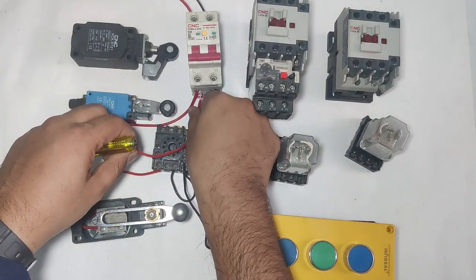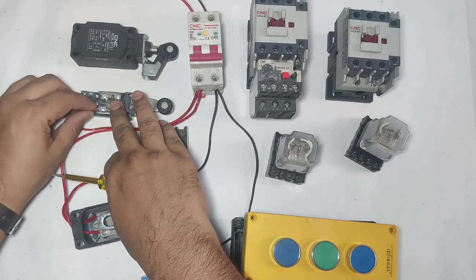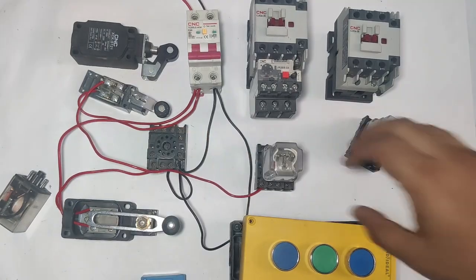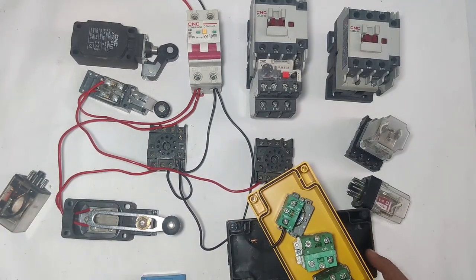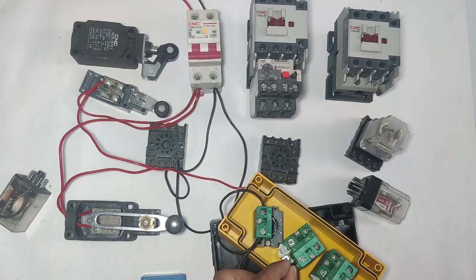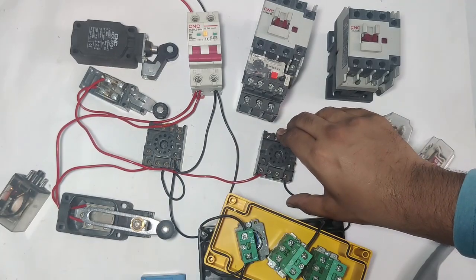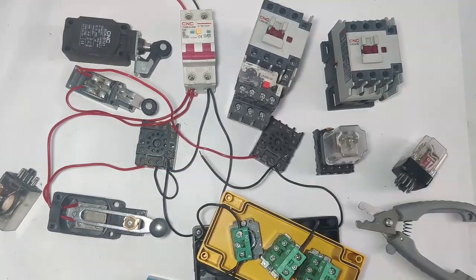First, take a connector from MCB and connect to the limit switch common and NC point. We use the limit switch NC point. The NC output connects to relay coil pin 10. For neutral, take a connector from MCB neutral — since neutral already comes into the ground floor push button, take a connector from that input and connect to the first floor N.O. element. When you press this N.O. element, R2 relay operates.